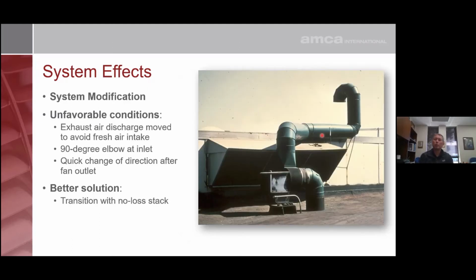Sometimes system effects are a result of design issues or design flaws. Here we have the clean air intake into the building. This fan is exhausting fumes from all the lavatories or bathrooms within the facility. When they started having complaints from the people inside the building about odors, they designed this nice little cowl system to redirect that foul air away from the clean air intake into the building.